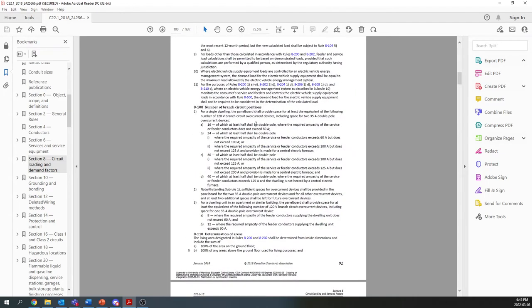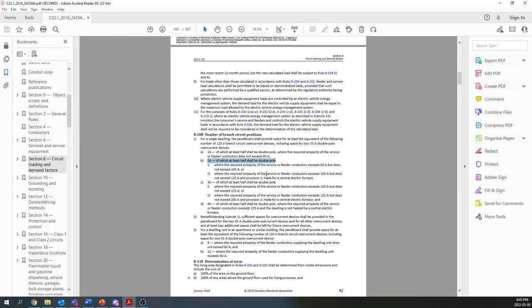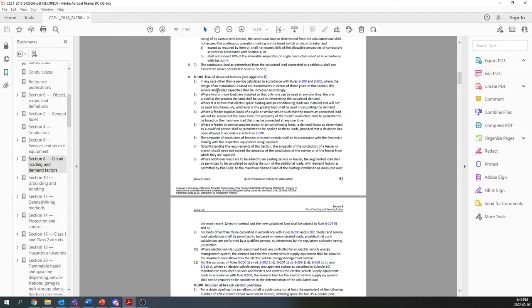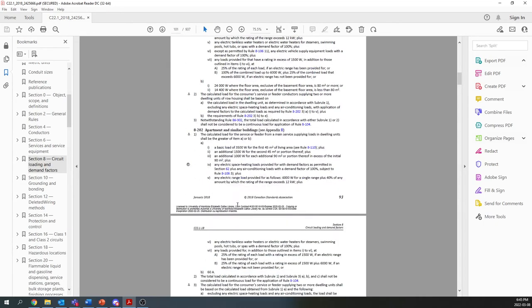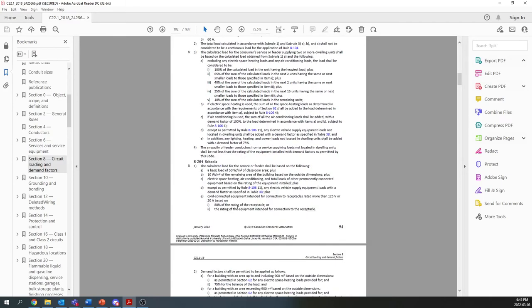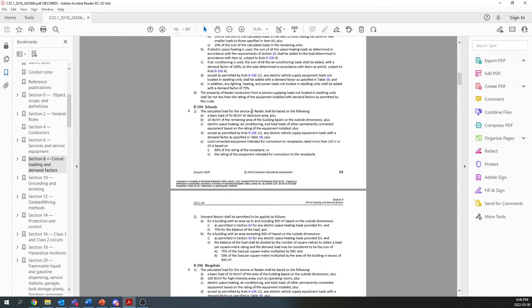There are other parts here of rules, for example, how many branch circuit breaker positions you need in your main panel board for a given panel board size, and how the demand factors are used, that sort of thing. So it defines, when a new building is generally being constructed, the designer, the electrician, the engineer has to know what size of service to design for. So this section actually outlines how, for example, if you're designing a new school, you decide, is it going to be a 500 amp service, a 200 amp service, 1,000 amps, who knows?